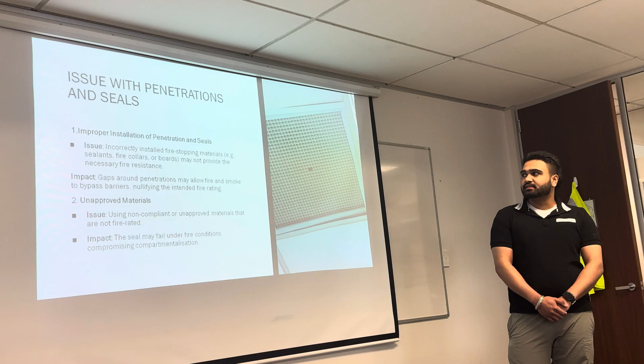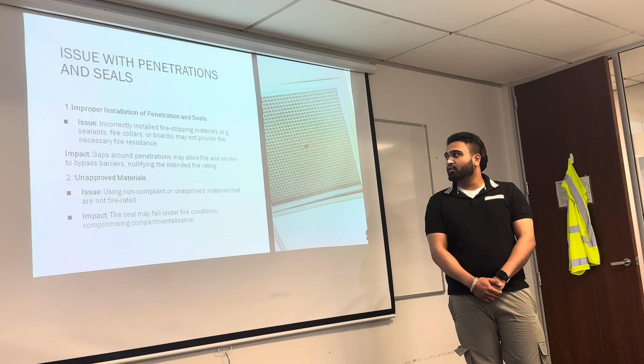The first one is issues with penetration and seals. The first is improper installation of penetration and seals. The issue: incorrectly installed fire stopping material, for example sealants, fire collars and boards, may not provide the necessary fire resistance. Impact: gaps around penetrations allow fire and smoke to bypass the barrier, nullifying its fire rating. In this image you can see a gap and hole, so smoke can pass easily.